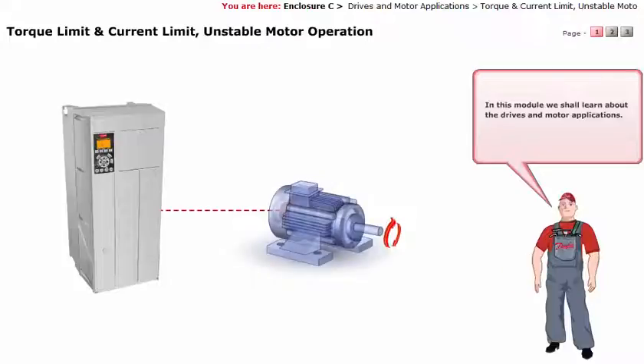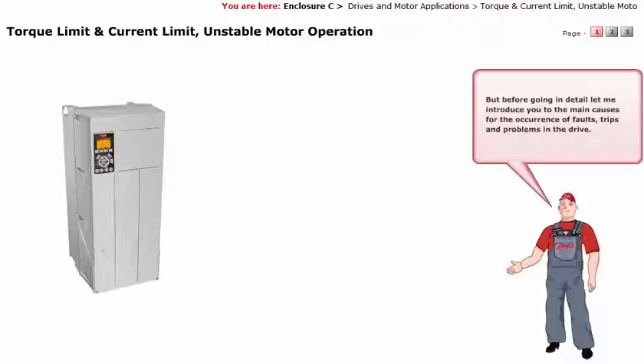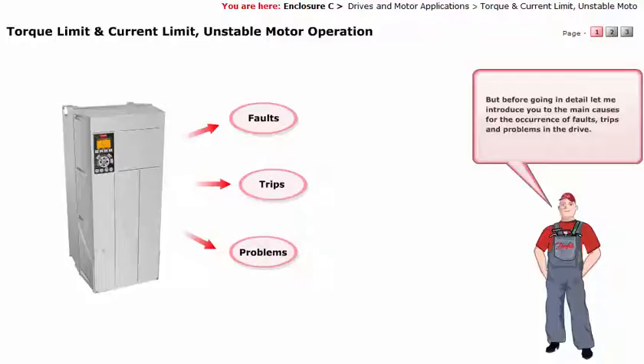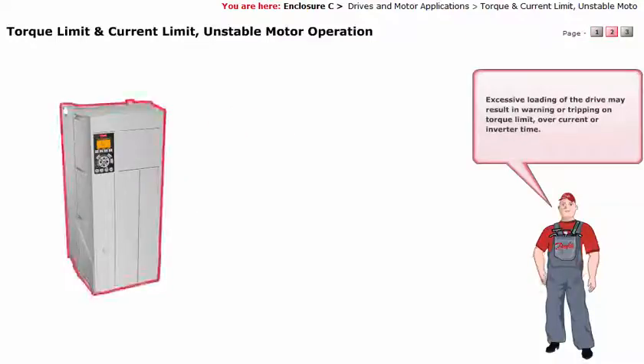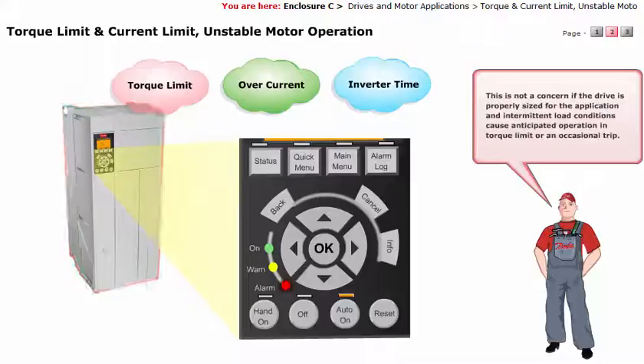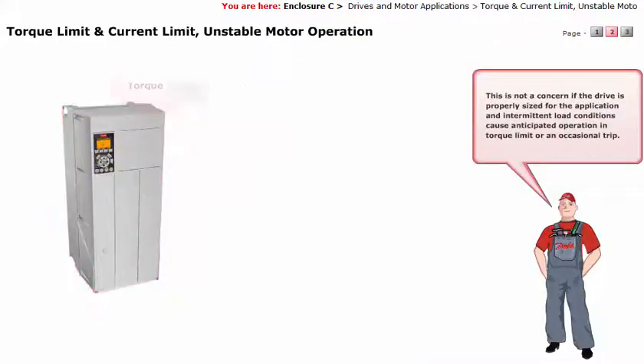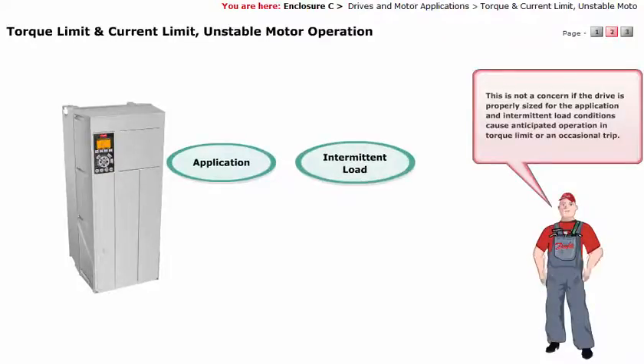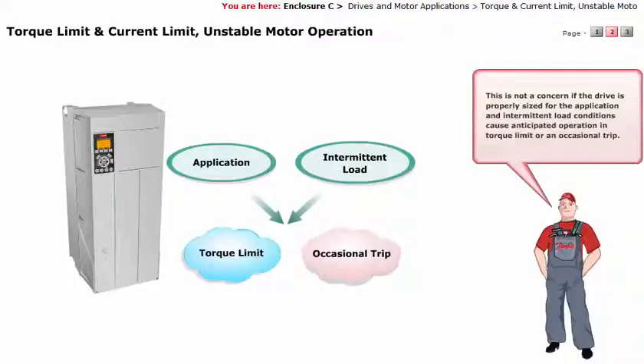In this module, we shall learn about the drives and motor applications. But before going into detail, let me introduce you to the main causes for the occurrence of faults, trips and problems in the drive. Excessive loading of the drive may result in warning or tripping on torque limit, over current, or inverter time. This is not a concern if the drive is properly sized for the application, and intermittent load conditions cause anticipated operation in torque limit or an occasional trip.